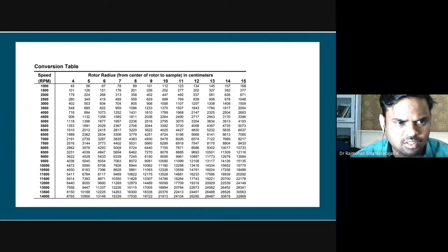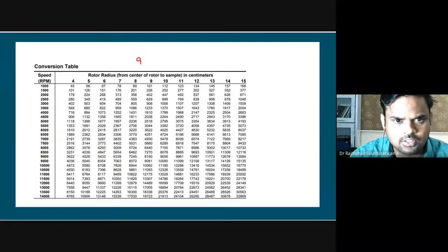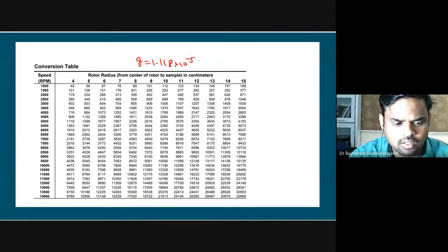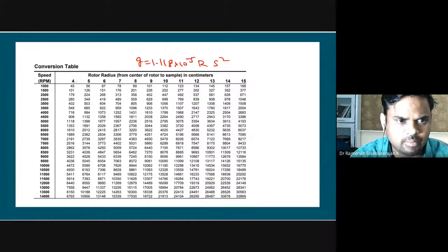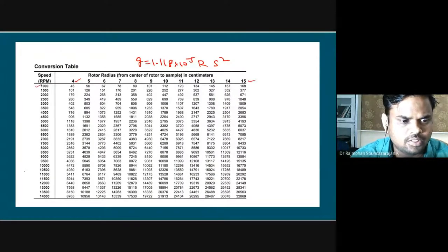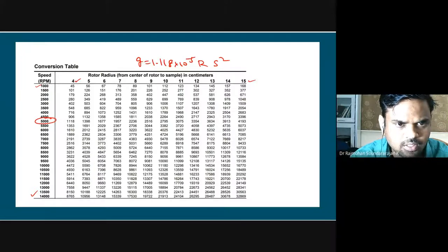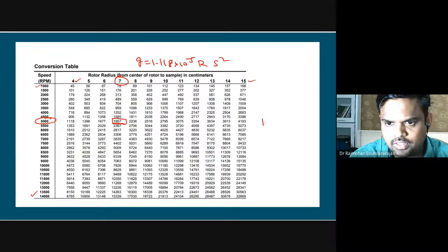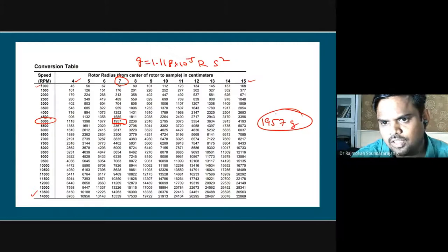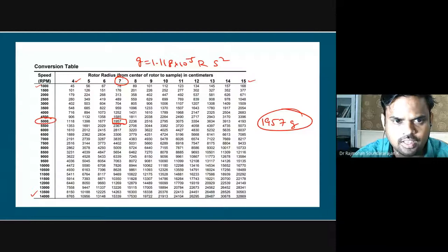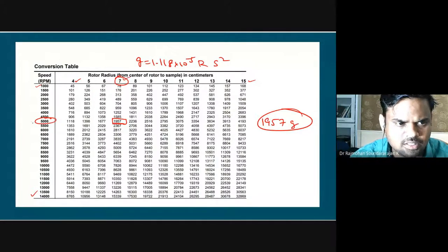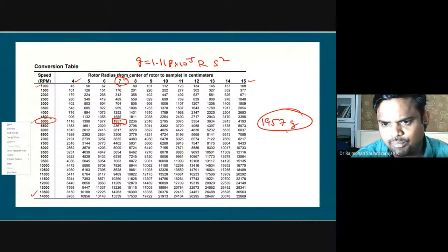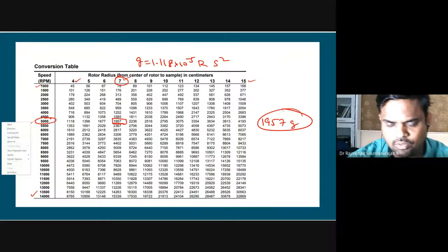A conversion table can be made using G = 1.118 × 10⁻⁵ × R × S², with radius from 4 to 15 centimeters and RPM varying from 1,000 to 14,000. At 5,000 RPM and 7 centimeter radius, the value is close to 1,957 times G. For a bench-top micro centrifuge used in the laboratory - like using a kitchen mixer - for batch operations, the speed and time are sufficient to ensure cells and debris are pelleted effectively. If sufficient time and speed are given, we can take out the intracellular fluid and its constituents. For industrial operations, energy and material balance require optimizing time and speed.